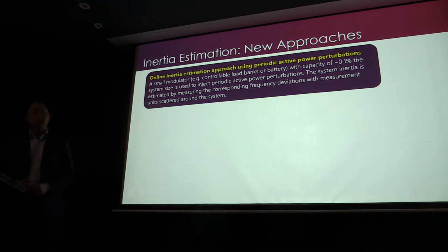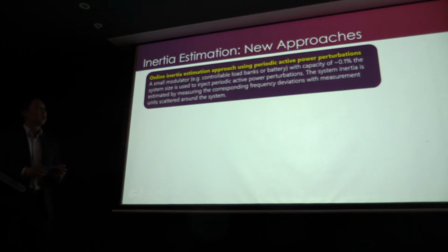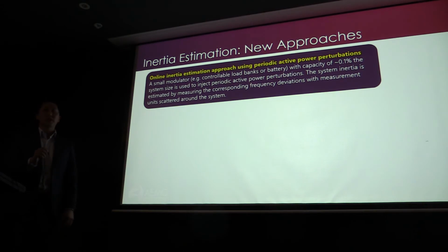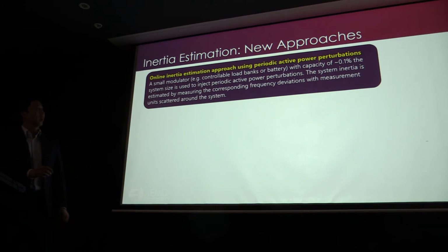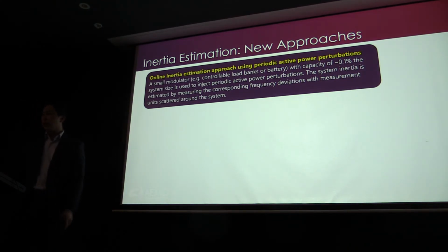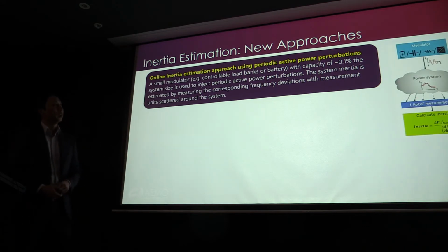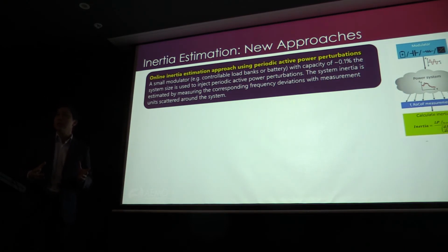Some other approaches: this is a really interesting and innovative approach to measure inertia online, and what it does is actually try to perturb the power system. You're injecting active power into the power system, and then trying to measure what you get on the other end. What you're perturbing it with is an oscillating frequency. So this is what it looks like. You've got a modulator, which could be a big battery, and it's injecting a sinusoidal frequency into the power system at some megawatt value.